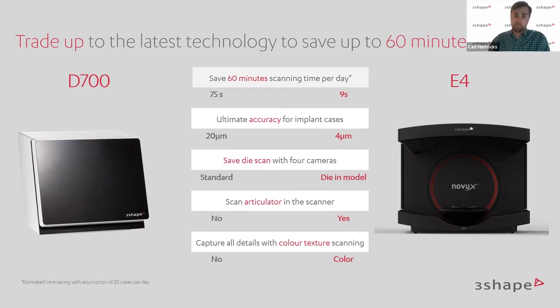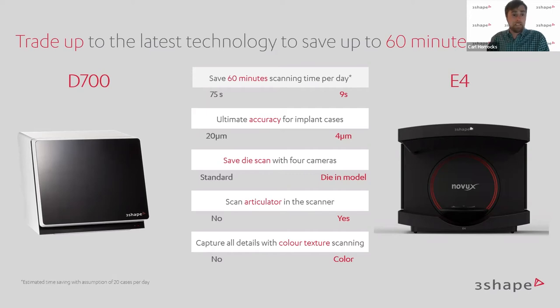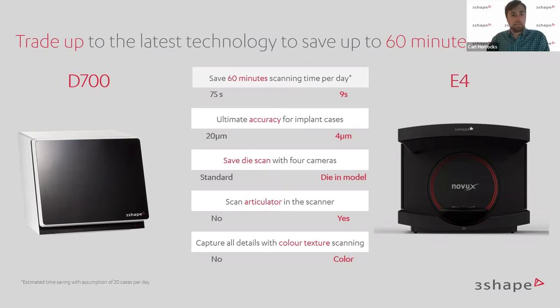Accuracy improvements: 20 microns versus 4 microns — you're getting an almost point-to-point perfect scan. And some things not factored into that one-hour savings: if you have a full arch restoration articulated on a physical articulator, with a D scanner you can't scan it with the full articulator — you'd have to unmount it, scan it, then remount it. But with any E scanner, you can stick a full articulated model right into that scanner. Probably the biggest way to save efficiency is upgrading out of a D scanner to any of the E scanners.